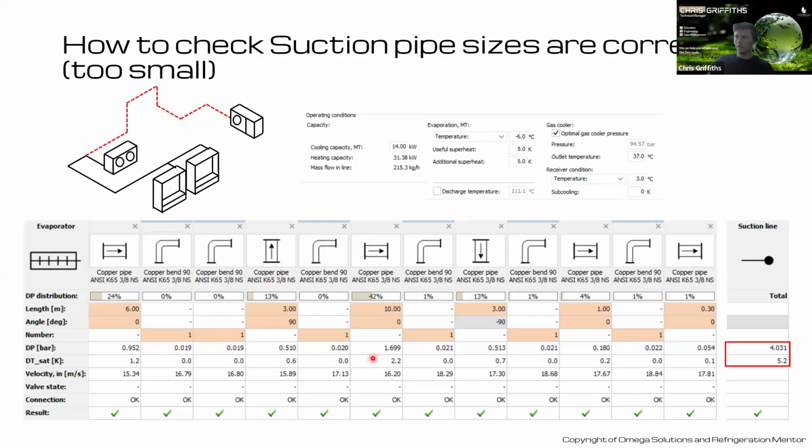Well, our straight length of pipe immediately after, it's 10 meters, 30 feet. We've got a pressure drop of 2.2 Kelvin, nearly 5 Fahrenheit there alone. That's a huge drop. In reality, if I was concerned that the velocity would need to be that high, I would say you'd step all the other pipe sizes up by 1 size, up to 1/2 inch, and leave the riser at 3/8. But we can probably get away with stepping that up as well.